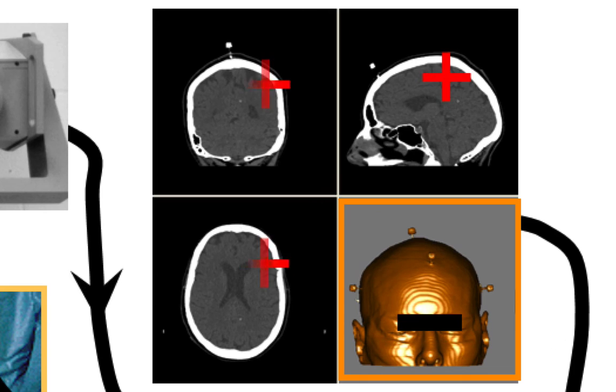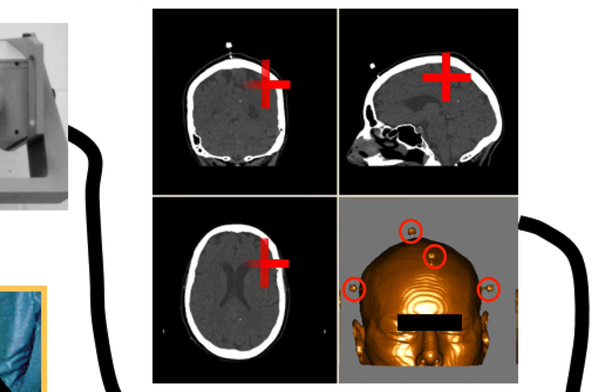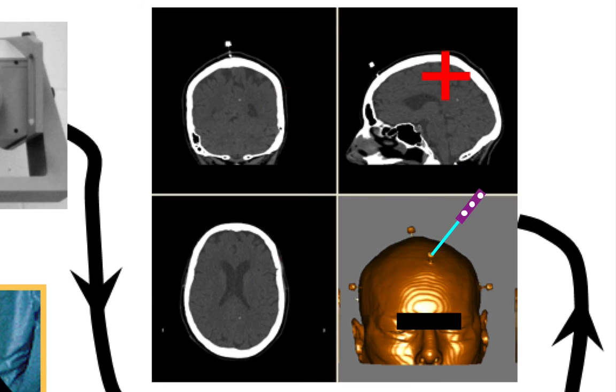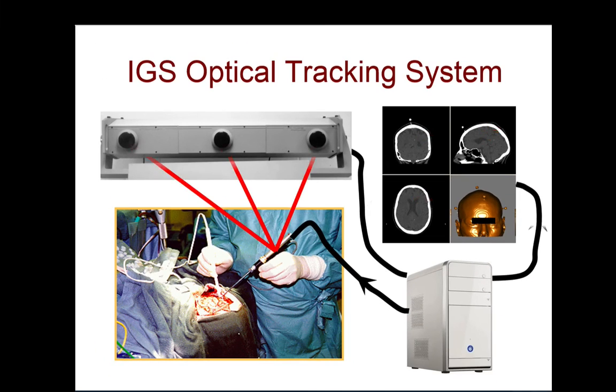You can see in that rendering that there are fiducials on the patient's head. Those fiducials were identified earlier in the OR by placing the probe sequentially in each of the fiducials. The computer then lines up the CT image so that it can show where the probe is located in the three views.